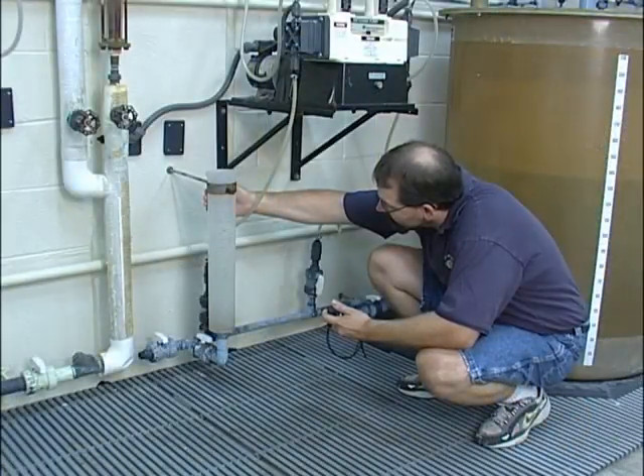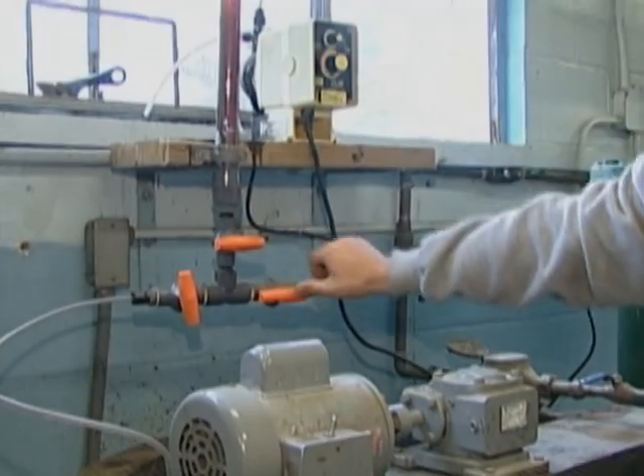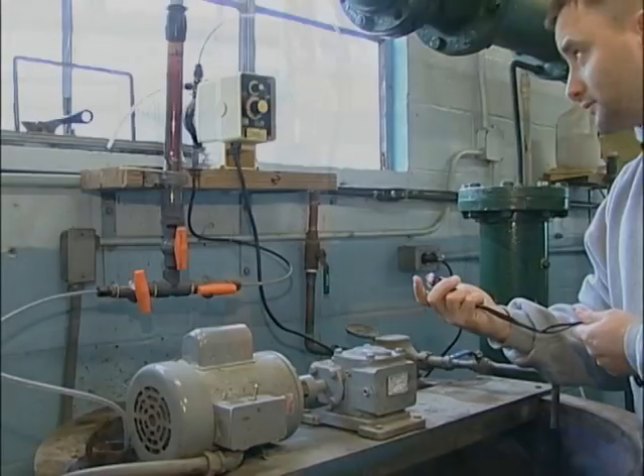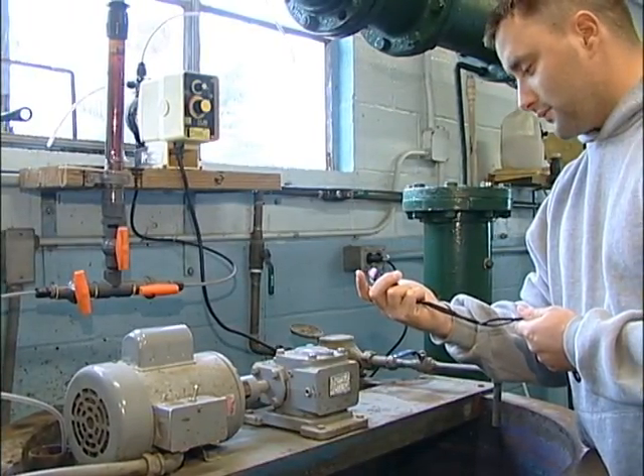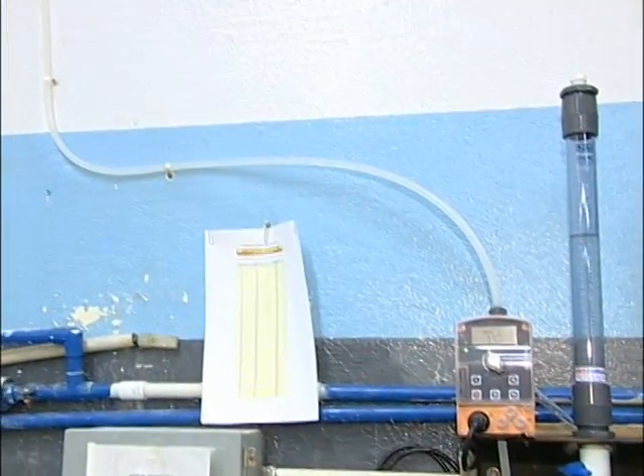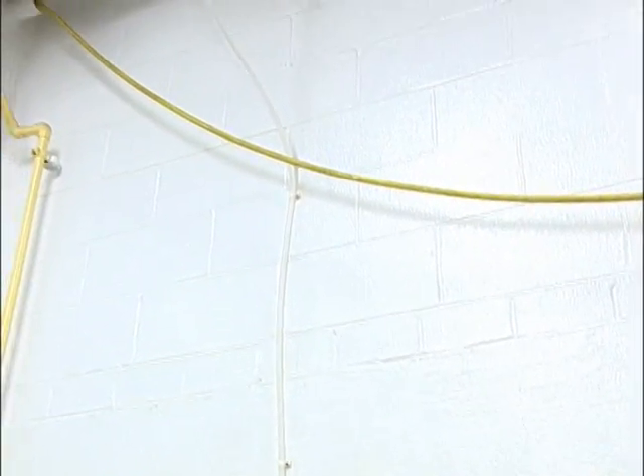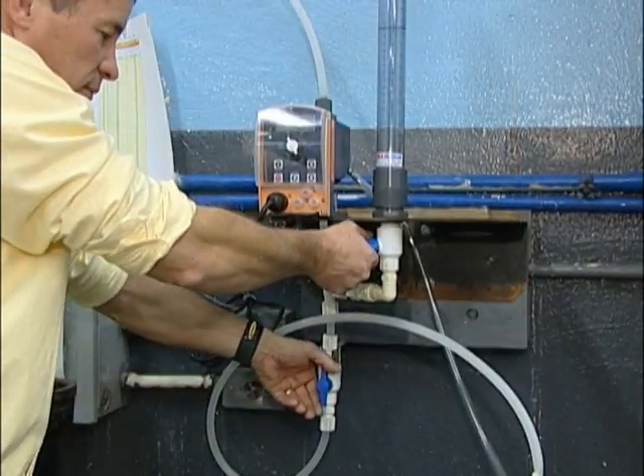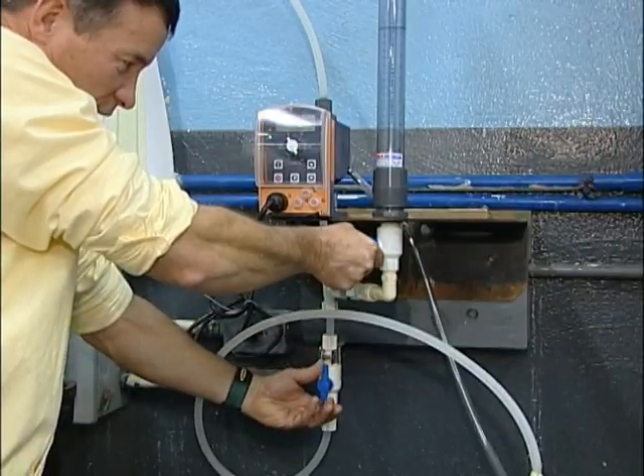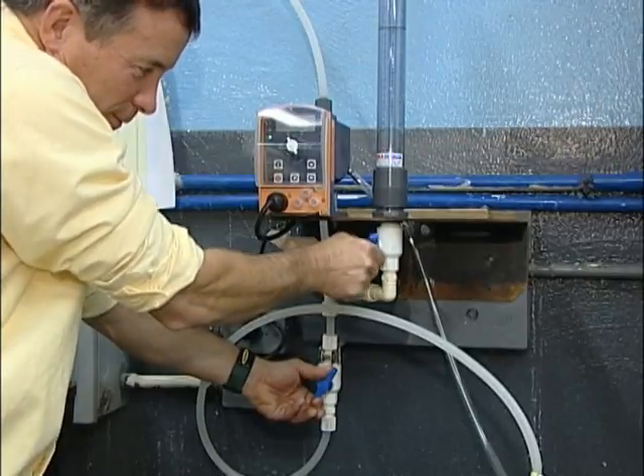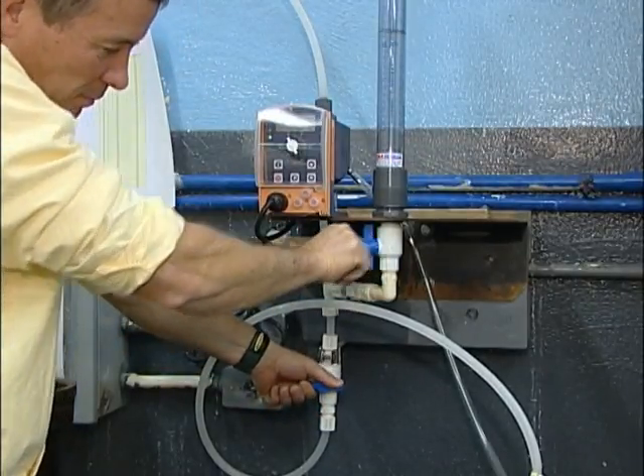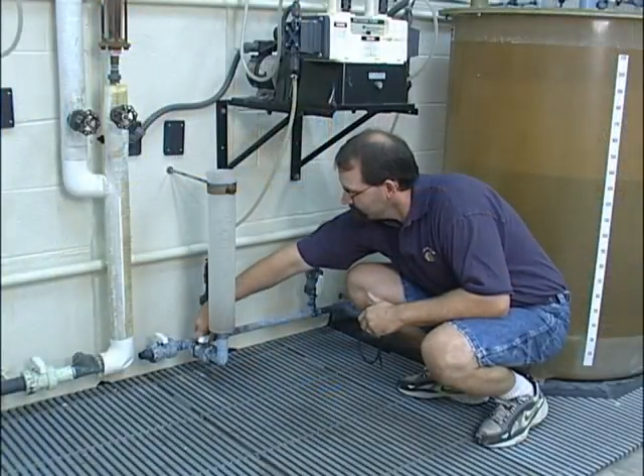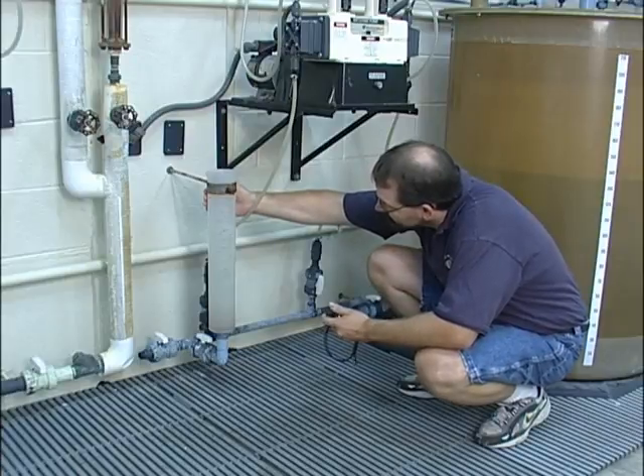The calibration tube can be installed in line on the chemical feed line using two valves and unions. This is the optimal arrangement for doing pump calibrations because it uses the chemical to be pumped and operates under the actual pressures and conditions of normal usage. To do a calibration, fill the tube with the liquid to be pumped. This is easily done if the tube is connected in line with the chemical feed barrel. The operator needs to close the valve to the pump and open the valve from the chemical feed barrel and to the calibration tube. Once the tube is filled, the valve from the chemical feed tank is closed, and the valve from the tube to the pump is opened.